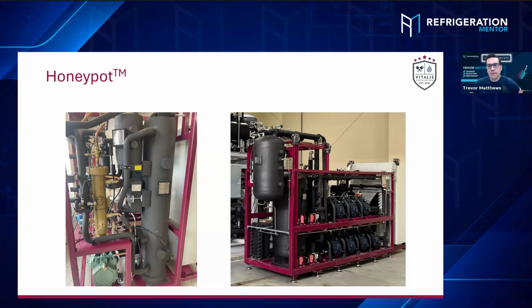But you will always pump in some air as well. It will never be just pure oil. So you would need to run the vacuum anyways. So it might go faster, but you need to run a vacuum no matter what. But you can always pull oil in while pulling the vacuum.